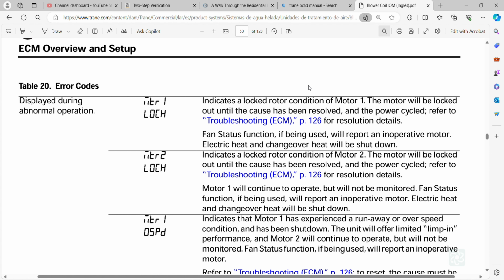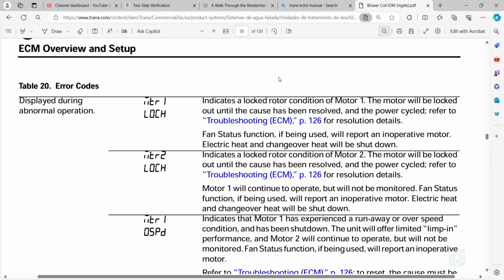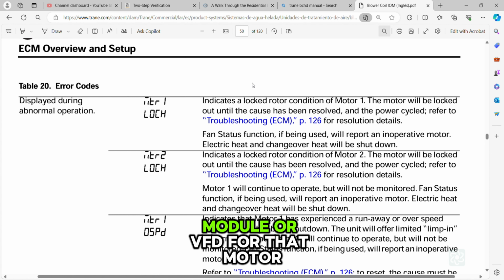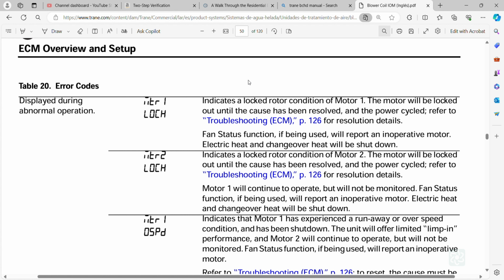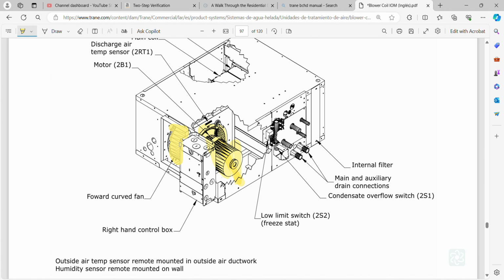So you want to check for correct outputs from that board and correct high voltage going to the module or VFD for that motor. Also want to check for side-to-side shaft play or a locked up rotor, of course, on the motor itself. There's no way to clear this error code though, so besides maybe resetting a circuit breaker or disconnect, you'll have to fix the problem before you'll reset the error code.